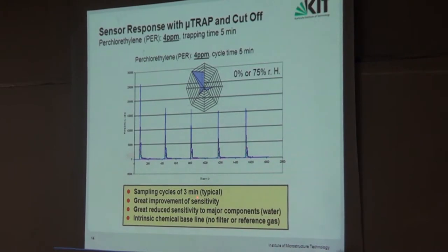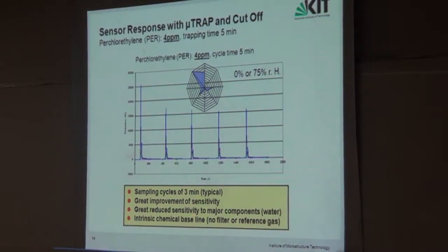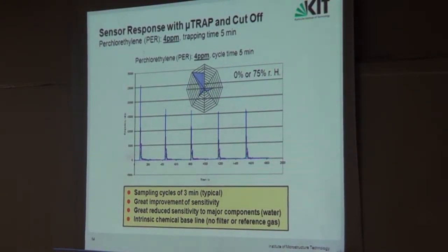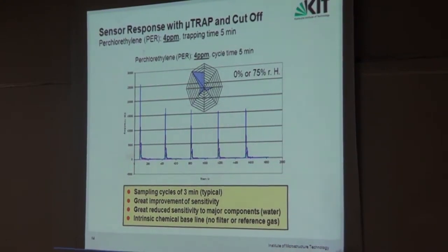The advantages of this approach include typical sample cycles of three minutes, a great improvement in sensitivity, greatly reduced sensitivity to major background components like water, and a self-built baseline — we don't need a clean reference gas bottle or filter anymore. This makes it a perfect setup for a continuously running room contamination monitor.